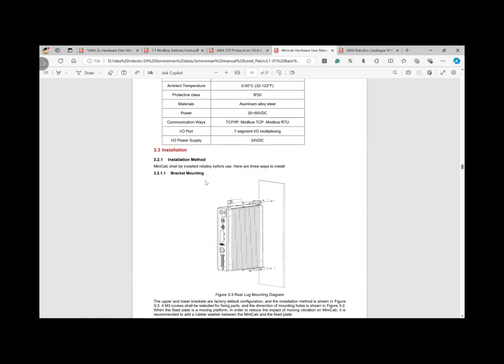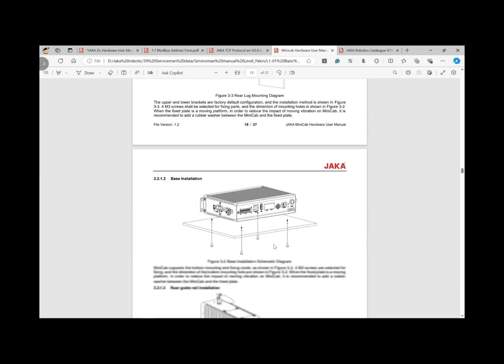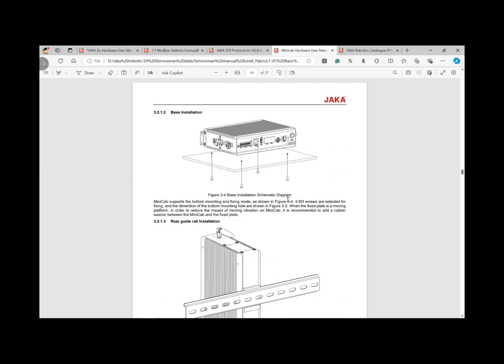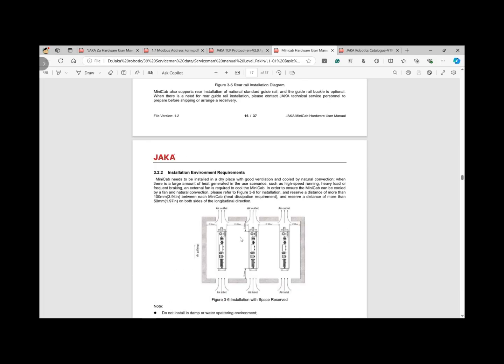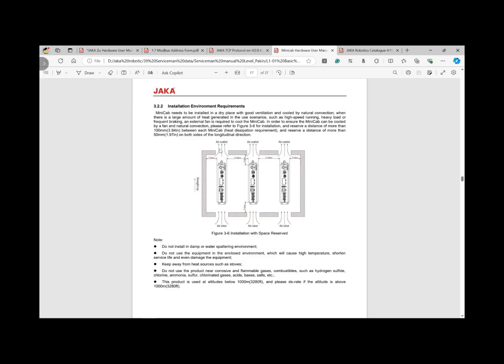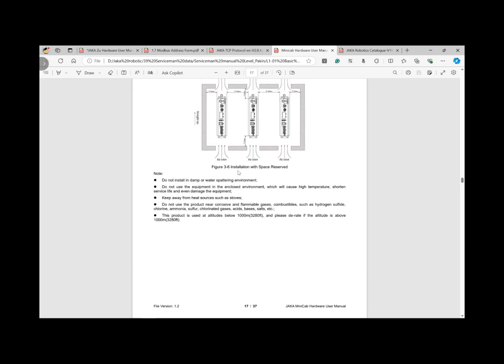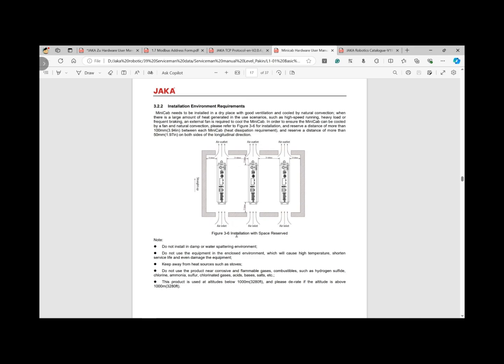Next, the mounting method. For the MiniCab, we don't recommend putting it directly on the ground. We recommend attaching the MiniCab to a plate, and then mounting that plate, not placing it on the ground. This is because the MiniCab is very small and needs airflow to keep it cooler, so every time you install the MiniCab, make sure there is enough space for air to circulate around it.